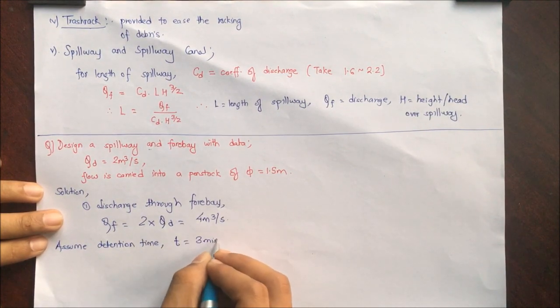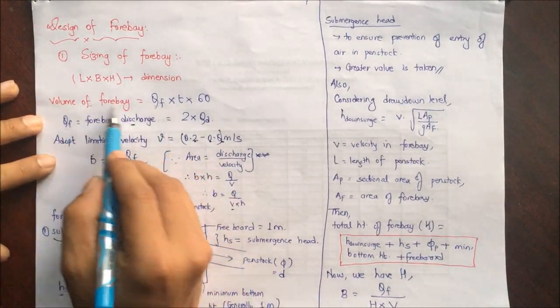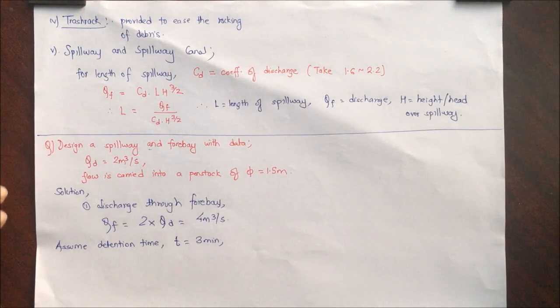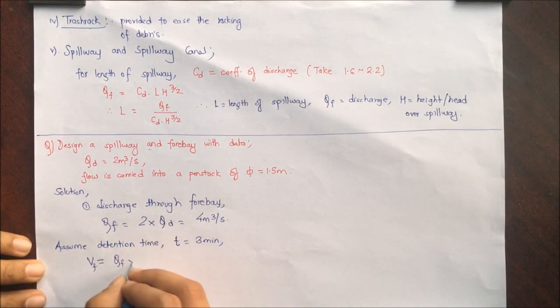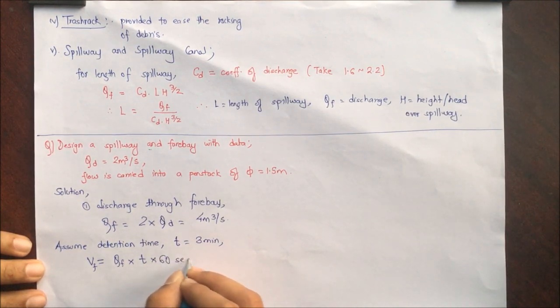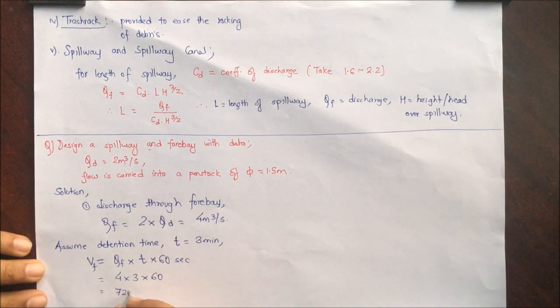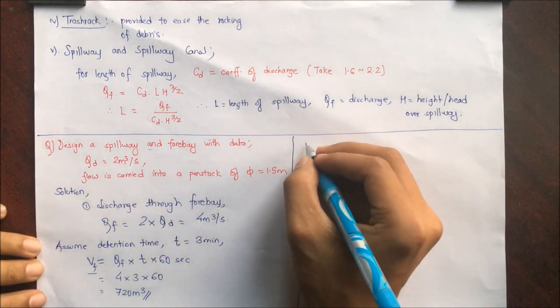Volume of forebay can be computed as Qf × T × 60, converting detention time in minutes to seconds. So Vf = Qf × T × 60 = 4 × 3 × 60, which comes as 720 meter cube. Now we have to calculate the height of the forebay.